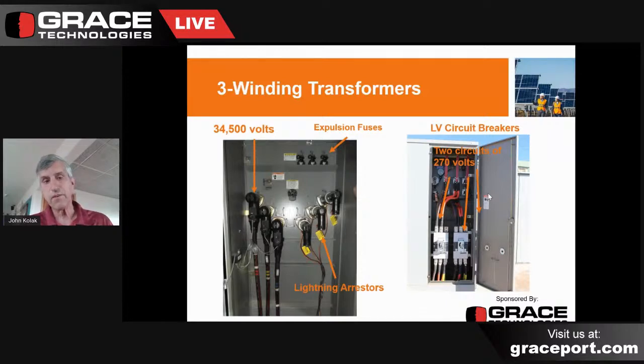So in this case, we've got the left side of the high voltage compartment there where we have our 34,500 volt switches or feeders or conductors. Now, again, when you look at the transformer, the H1A and H1B are the same conductor. There's a bus bar that goes between it, and it feeds through. In this case, this would be the last transformer in a string of transformers or a circuit of transformers. And you'll notice the very last thing we have on there is elbow-mounted lightning arresters.